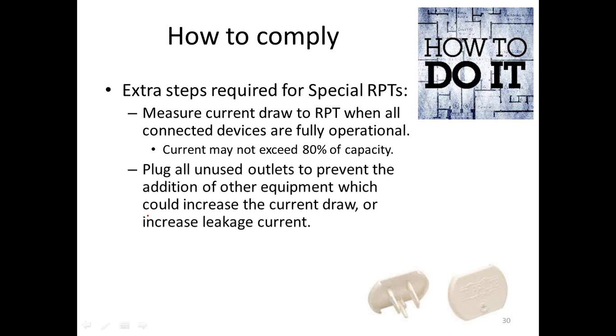So you plug in, and then you have to plug up all of the unused outlets to make sure people don't come along and plug in unused equipment and exceed that 80 percent capacity. You see these little plugs down at the bottom? These happen to be made by Tripp Lite. You can go out and buy child-proof connectors from Walmart or Babies R Us or somewhere and plug those in, but people can take those out. I particularly like the Tripp Lite ones because they expand. You can look right down here and see there's a little outlet with a little Phillips screw. When you plug this thing in, you push it in and it expands, and it won't come out unless you have a Phillips screwdriver, so it protects it from the average nurse being able to get in and plug other stuff in.